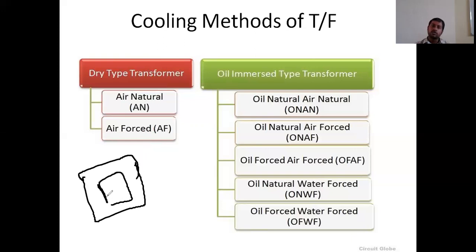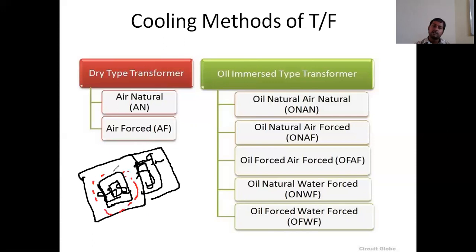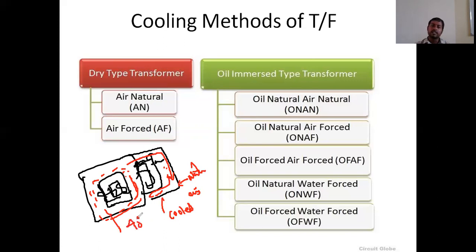In the ONAN system, this is the transformer core inside the tank, with outside radiators available. Whatever heat is available in the transformer tank will circulate into the radiator pipes. Because of natural air, the oil inside the radiators will be cooled. For example, if the inside temperature of the transformer tank is 40 degrees centigrade and in the radiators the oil temperature is 35 degrees, to balance the temperature levels, cooled low-temperature oil is sent to the transformer tank and high-temperature oil is sent to the radiators.